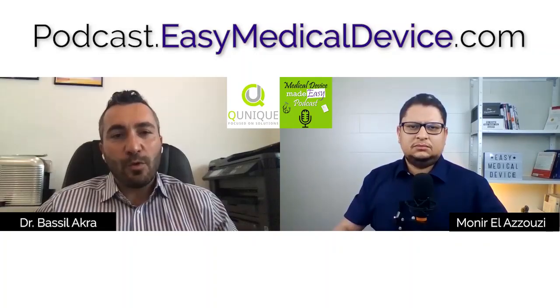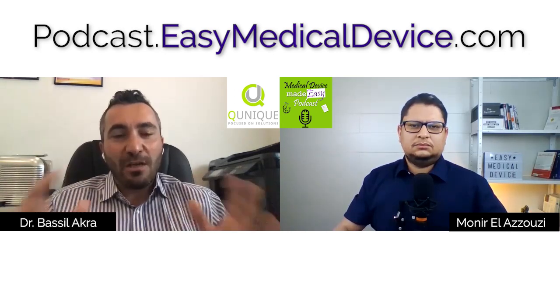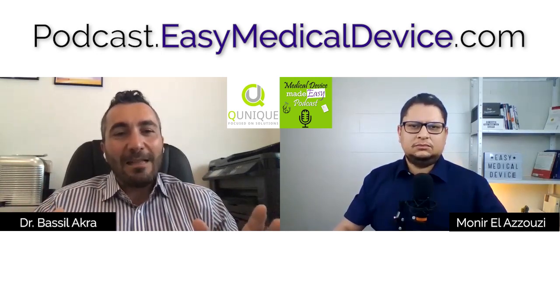If we look to the MedDev and we look to MDCG guidance documents, when we talk about the MDR framework, the MDCG guidance are referring to the MDR. Now, in the MDCG guidance, which were published recently, there is a reference to some MedDev. Why? Because the MedDev 2.7.1 revision 4, which you mentioned, is a guidance which includes two parts: the general clinical evaluation requirement and the specific requirement related to the MDD. When I talk about general requirements, this means how you do a clinical evaluation. This kind of requirement is still the same under the regulation.